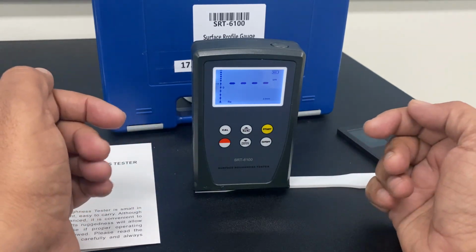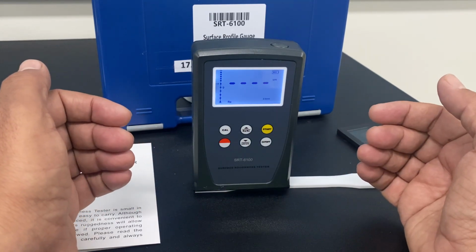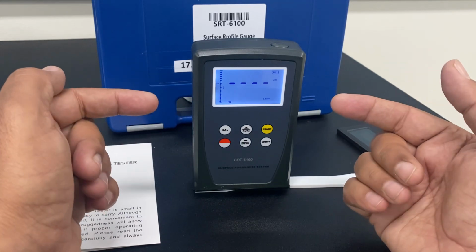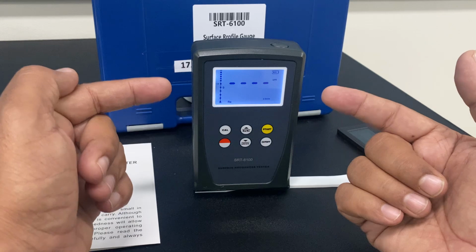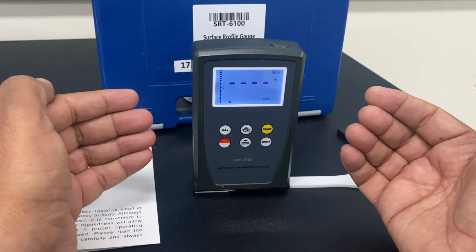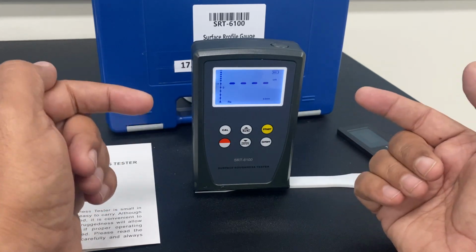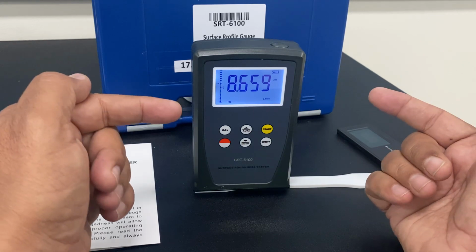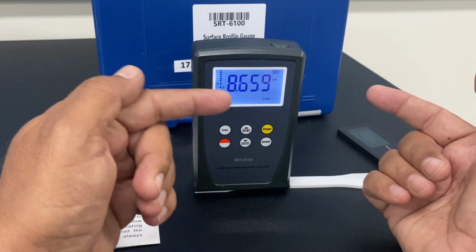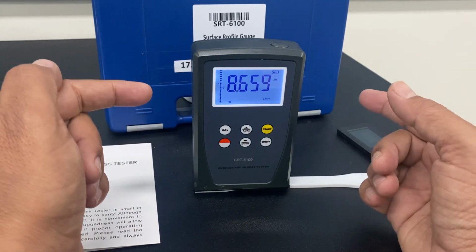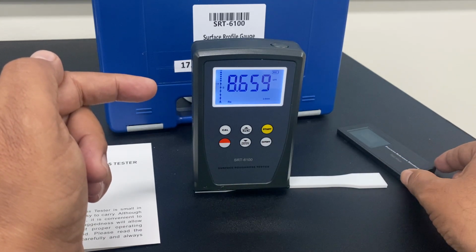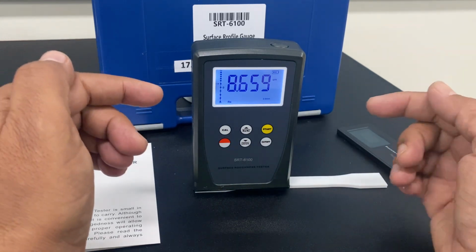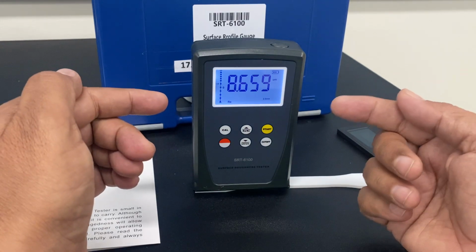Again, it will travel a short distance, that cutoff distance, and it will display the value of surface roughness Ra. You can see the value of Ra will appear on screen shortly, and I also know how much the error is. So 8.659 is the current value, and the error I also know because I used the calibrator initially. That error you have to subtract from the value that you get on screen.